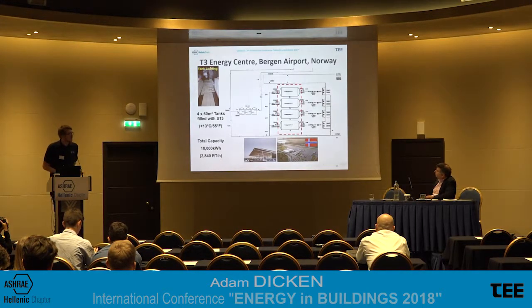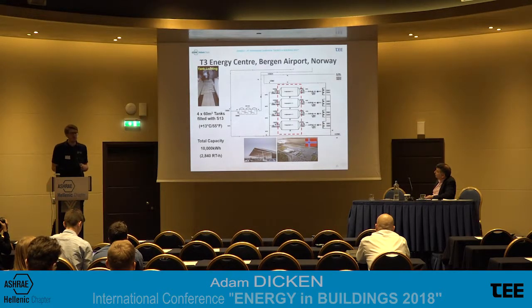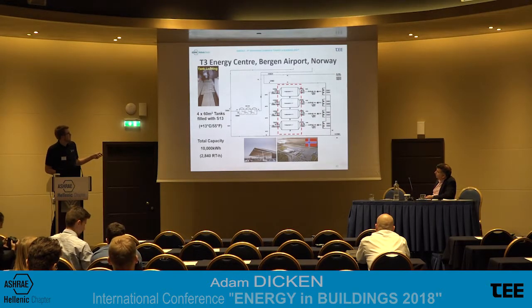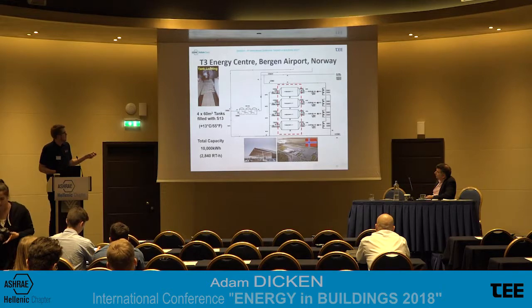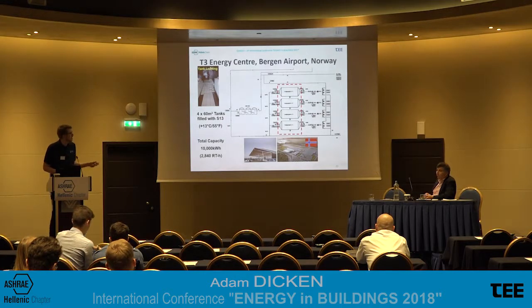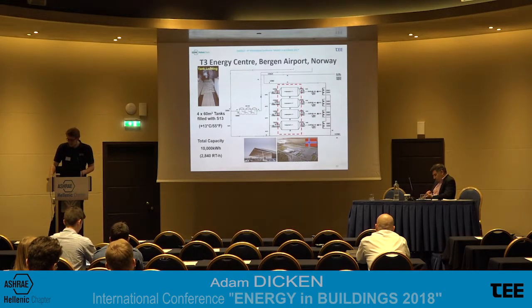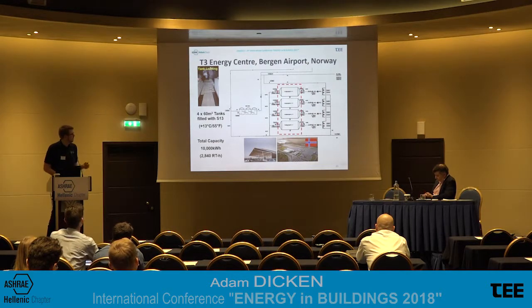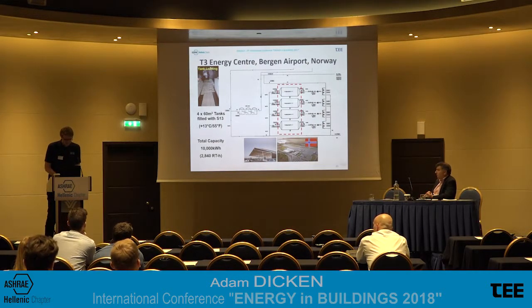An example of this is Terminal 3 at Bergen Airport in Norway, where they have 10,000 kilowatt hour PCM tanks, which is 4 of our 60 metre cube tanks, once again with stacked phase change materials. In this example, they run their chillers flat out through the night, building up a large reserve of thermal energy that they can access later.